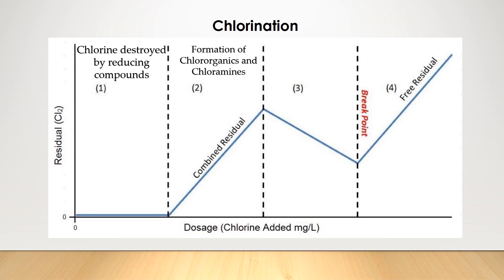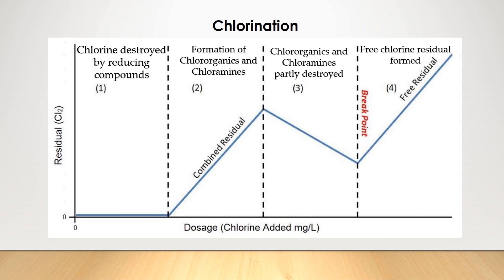We keep pumping more chlorine into the water and move into Stage 3. Here the chlororganics and chloramines that were just formed are now being partly destroyed — the chlorine you're injecting is actually destroying what you just formed. Then in Stage 4, free chlorine residuals are being formed and the blue line trends upward. The most important point on this graph is the dashed line between Stage 3 and Stage 4. That's where free chlorine residual starts to form, and if you follow that dashed line to the bottom, that's the chlorine dosage that will take you to the breakpoint where free chlorine residual will start to form.